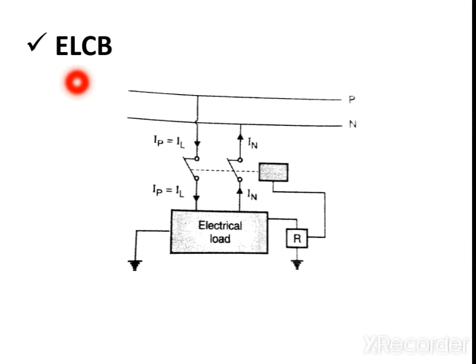The next protective device is ELCB. ELCB means earth leakage circuit breaker. We have seen MCB, that is miniature circuit breaker. This circuit breaker is used for overload protection and short circuit protection.